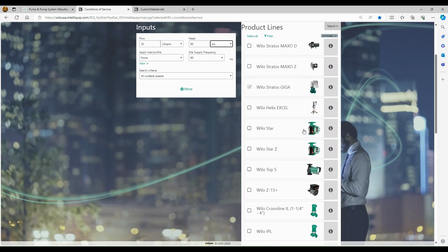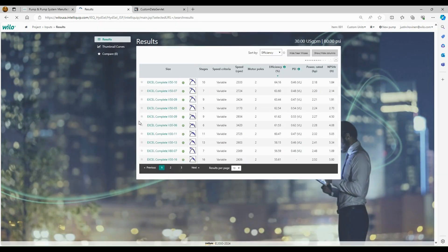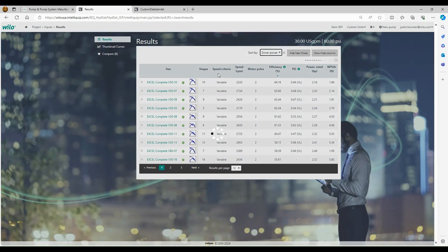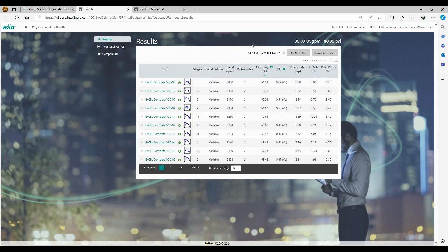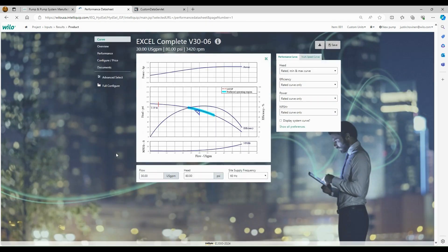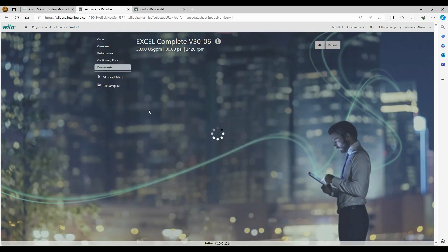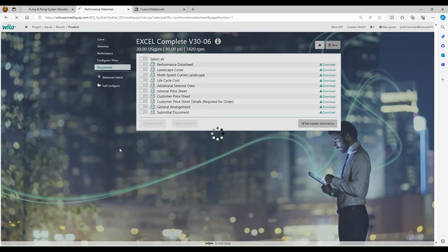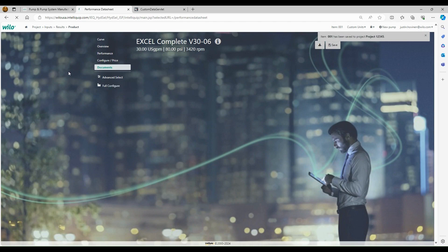So we'll just do 30 gallons a minute and we'll do 80 PSI. And then we will select the Helix Excel complete. This is our ECM simplex booster pump version. We'll click search. And then same thing. So it's given us a bunch of different options. It's sorting by efficiency. So we'll see it's the Helix V 50-10. So we'll change it to driver horsepower. And now we've just gone down in size and now we're at a Helix V 30-6. So if there's one takeaway, definitely sort by driver horsepower. So that gets us down to a three horse. And then we'll go in here. We'll configure and price. So everything, we'll do standard features. And then basically all we're going to do up here on the right hand corner is we're going to click save. It's thinking, usually it takes a few seconds. So that is save this project.